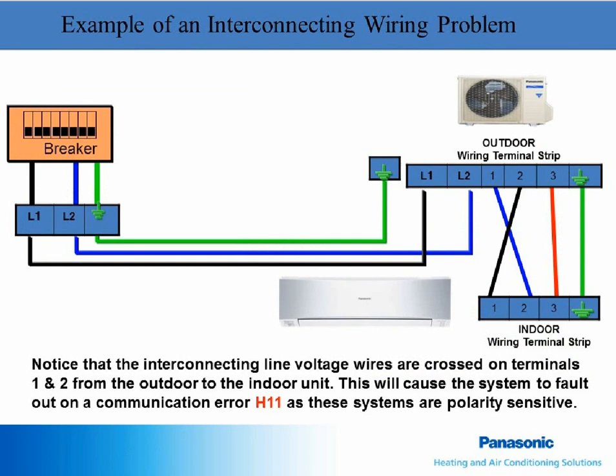The interconnecting wiring is simple, but mistakes can easily be made. The wires must be landed from terminal 1 outside to terminal 1 inside, then 2 to 2, 3 to 3, and ground to ground. Wired wrong, there will be communication errors and no heating or cooling.